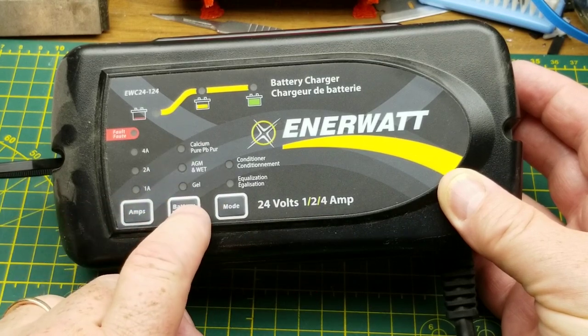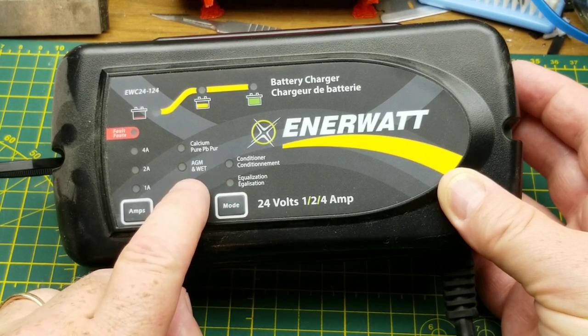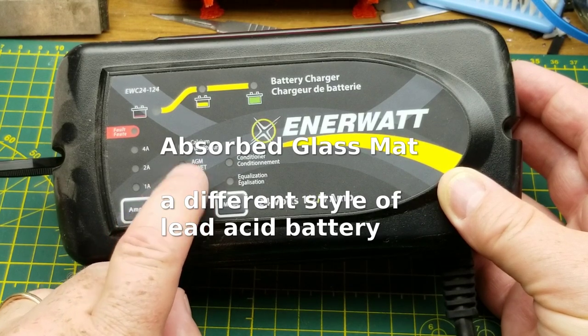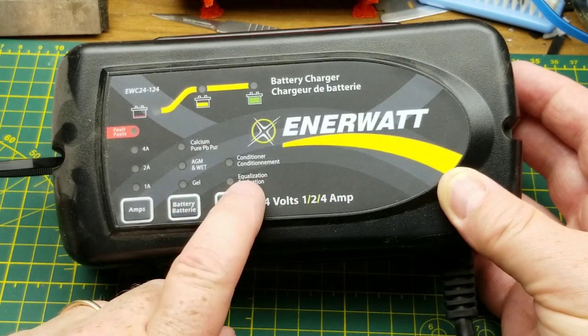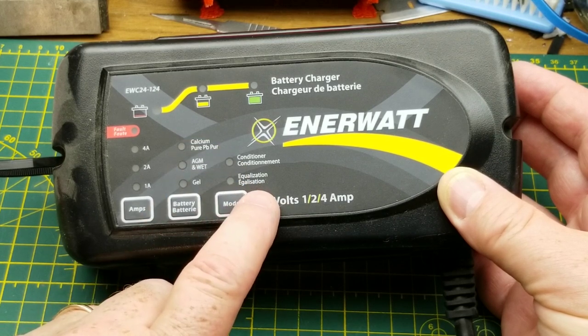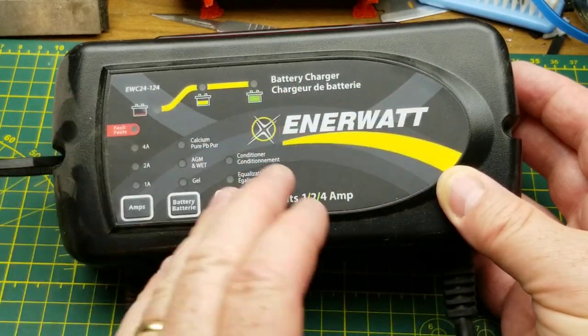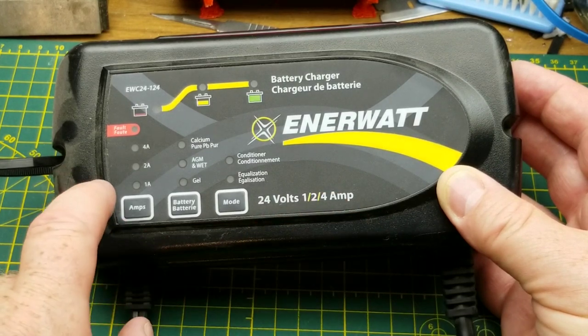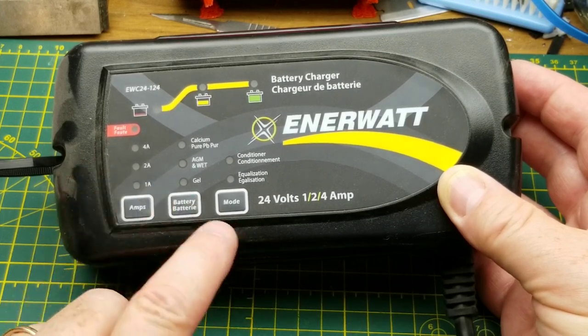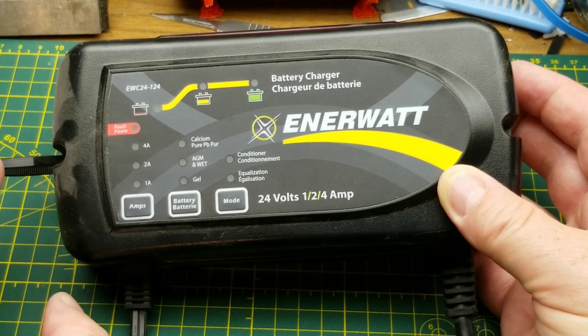This is an Enerwatt EWC24-124 — 24 volts, one, two, or four amp charging current. It can handle various chemistries: calcium, pure lead, AGM, wet cell, or gel cell. You can put it in conditioning mode or equalization mode — equalization mode basically boosts the output voltage a little to try and get each cell voltage more equal to the others. You can also set the charging current to one, two, or four amps. This one was left on a one-amp trickle charge to start the generator.